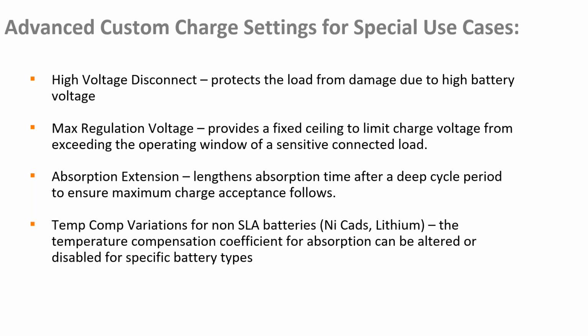Max regulation voltage is good as well. What it specifies is a max threshold on the battery side, so that your battery will never regulate to a voltage above that threshold. So if you specify the max regulation voltage is 15 volts, even with temperature compensation and really cold temperatures, it's not going to go above 15 volts, and hence the load connected to the load output terminals is not going to see a battery voltage higher than that 15 volts either. So it's a way of protecting both the load and the battery.